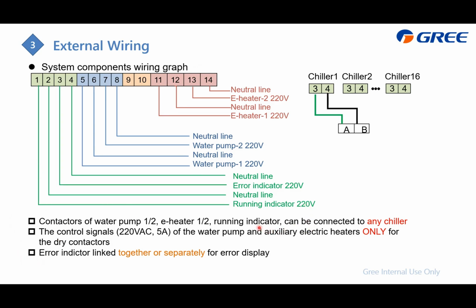For the modular system, you can connect the water pump, the e-heater or the running indicator to any chillers. To control the water pump or the e-heater, only a dry contactor or relay is used. And for the alert indicator or the operating indicator, they can be made together or separately.